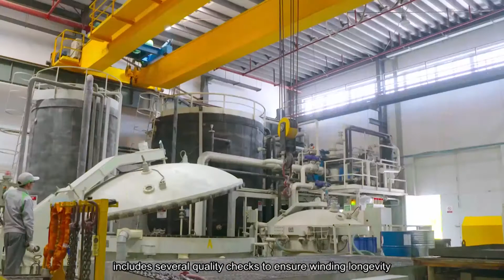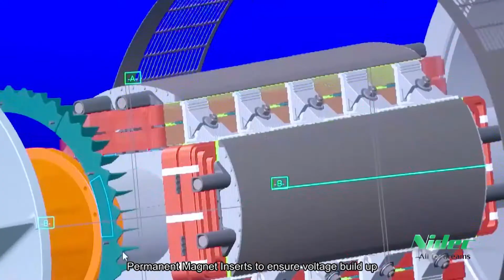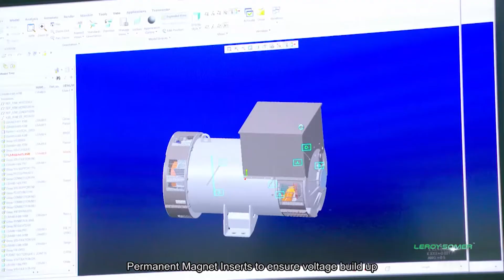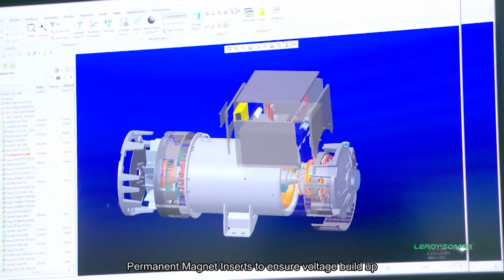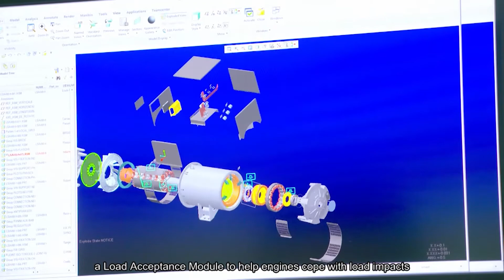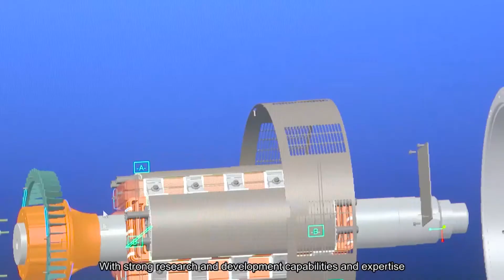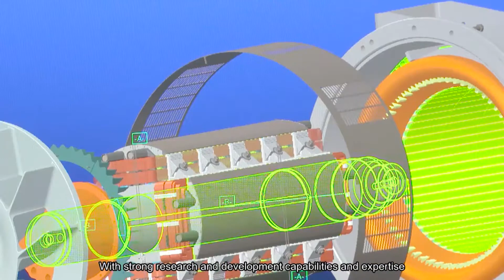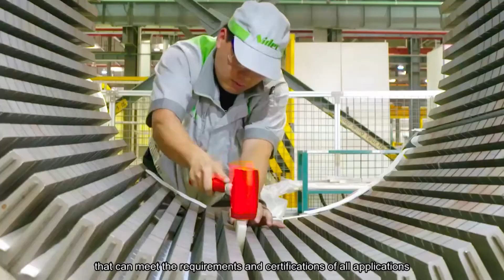Leroy Somer alternators feature cutting-edge technologies: the patented AREP excitation, auxiliary winding regulation excitation principle, for high short circuit and starting capabilities; permanent magnet inserts to ensure voltage buildup; and a load acceptance module to help engines cope with load impacts. With strong research and development capabilities and expertise, Leroy Somer designs products that can meet the requirements and certifications of all applications.